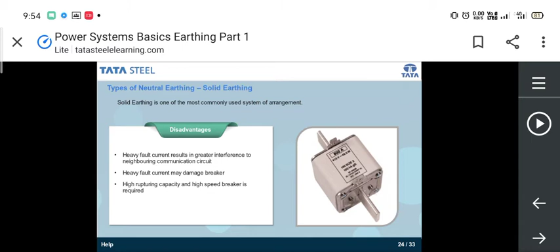Let's take a look. The first disadvantage is that heavy fault current results in greater interference to neighboring communication circuits. Further, heavy fault current may damage the breaker. Another disadvantage is that for this system, a high rupturing capacity and high-speed breaker is required. Let us move on to learn about resistance earthing.